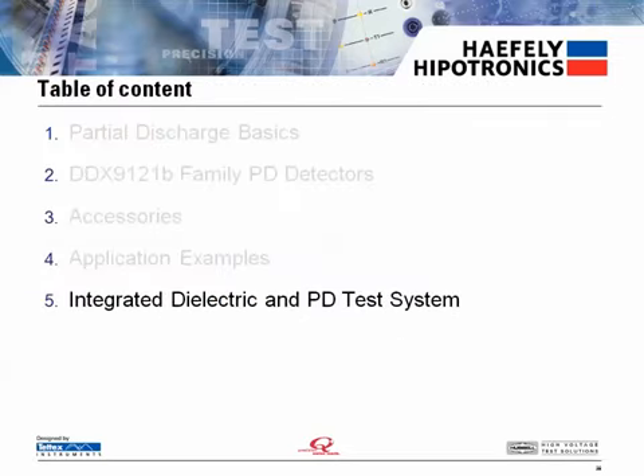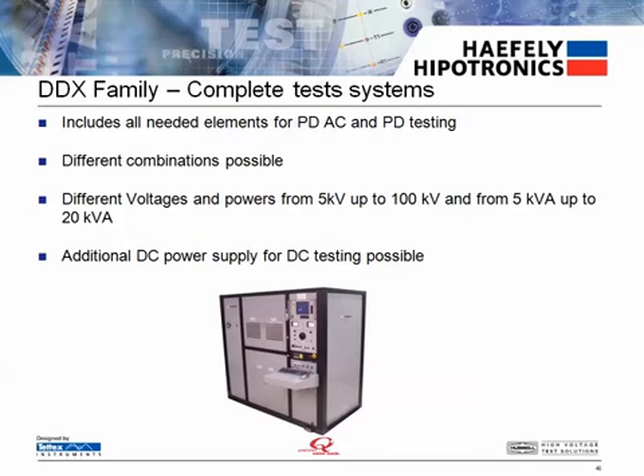We can also offer integrated PD systems for AC and DC solutions. These include the high voltage test source, coupling capacitor, detector, calibrator, and controls in a single cabinet system, along with a test chamber. We can offer these for a variety of voltage and power ratings depending on your application.